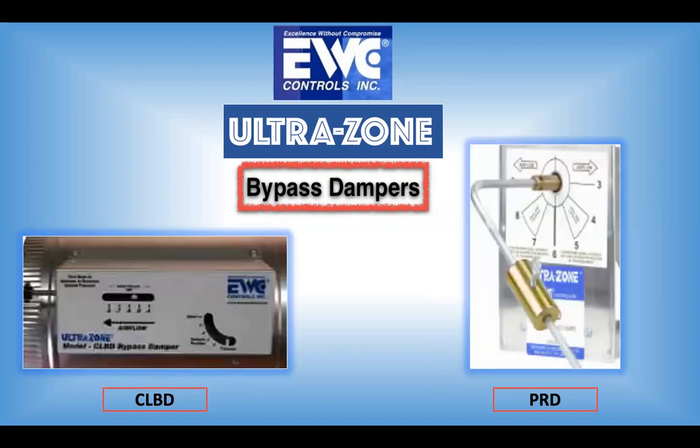So the rectangular damper still utilizes the arm and weight, meaning I've got to adjust my bypass damper blade based on the location of my arm and adjusting a weight up and down that arm. The CLBD incorporates a whole different style. We now eliminated the arm and weight, and we incorporate a very strong magnet with a very strong spring.